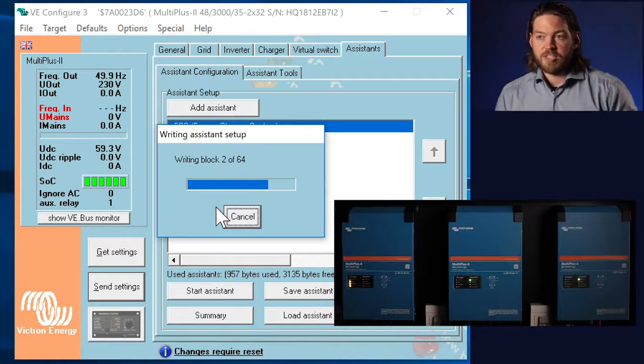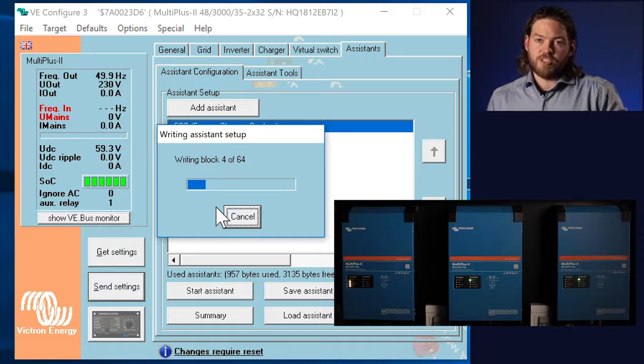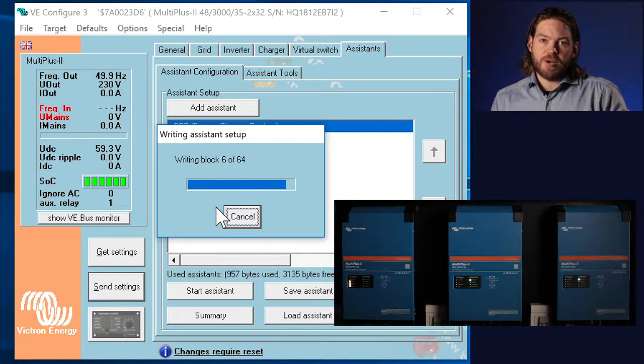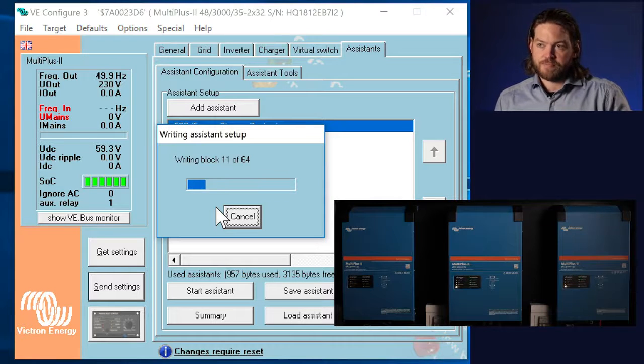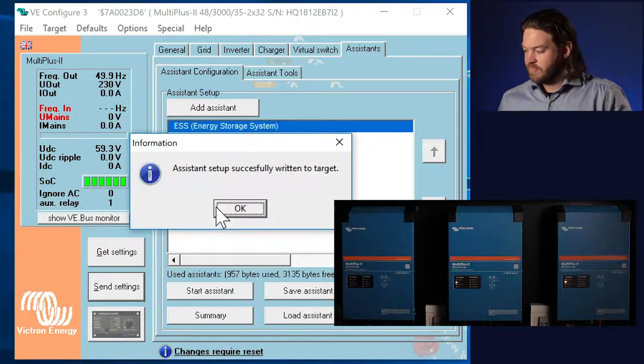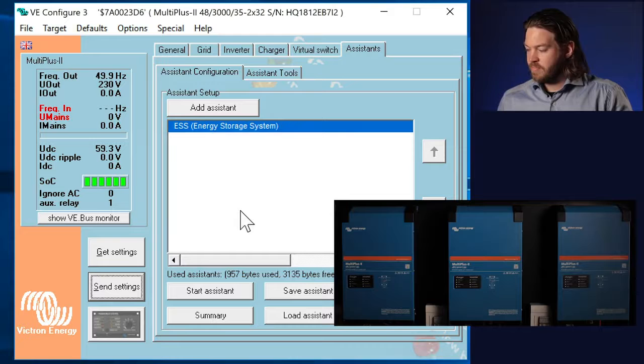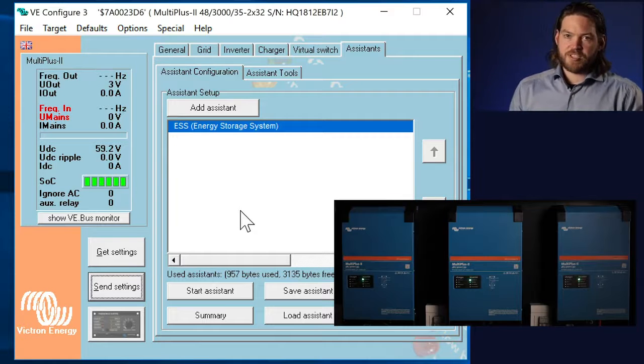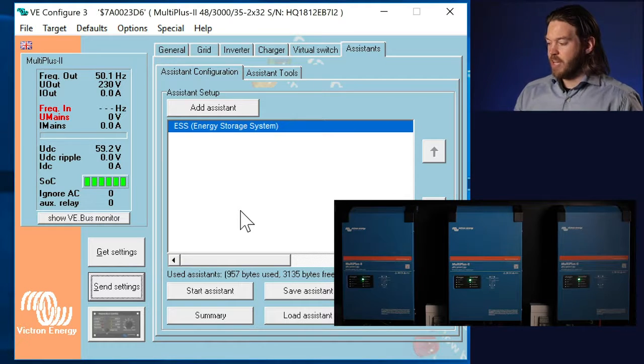Now, when I'm sending the assistant, one of the units which is receiving the assistant will switch off, and the other two units will drop out at the same time. In a three-phase and parallel system, all units must be on and working, or else none of the units will work. They rely on each other for synchronization. Once the configuration's been sent, all units will restart, and they should all connect and resynchronize with each other. The assistant's been successfully sent to the first target, and all the units are back on now.